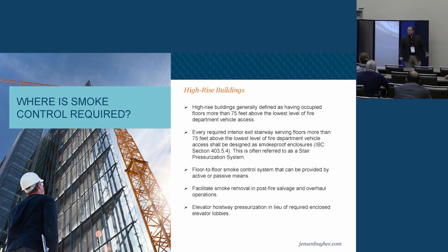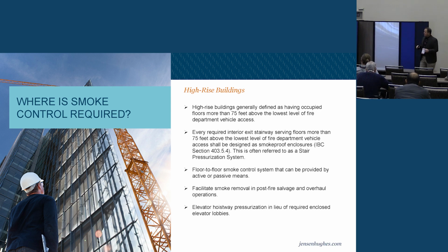All right, so where is smoke control required? The biggest one is probably high-rise buildings. A high-rise is typically defined, and I say typically, some jurisdictions define this slightly differently. Most of them define it as 75 feet from the lowest level of fire department access to the highest occupied floor. So anything over 7 stories-ish, you're probably into high-rise, right? If you have a building in that area, you probably have some type of smoke control, from basic to pretty complex. And I'll give you examples.